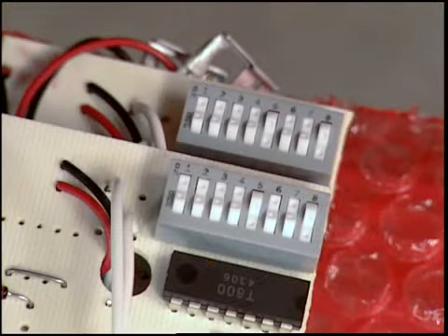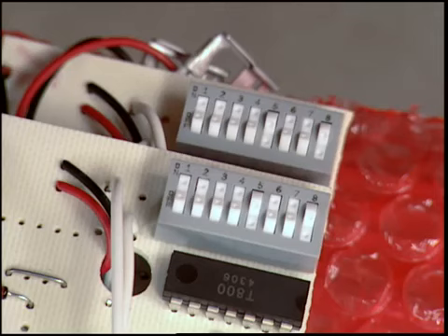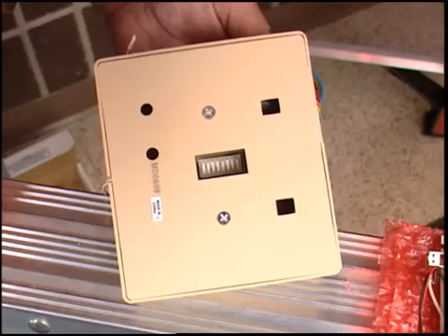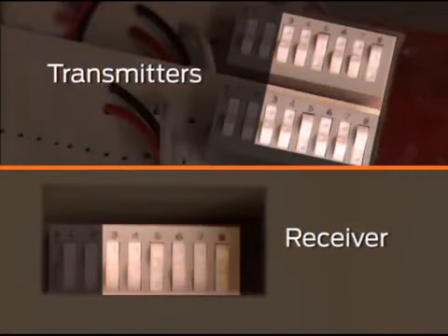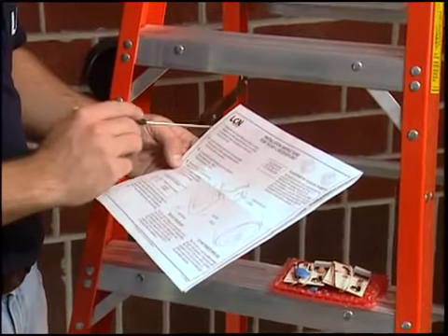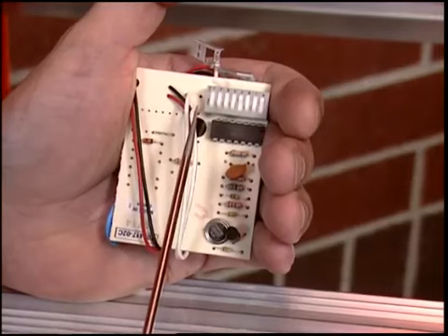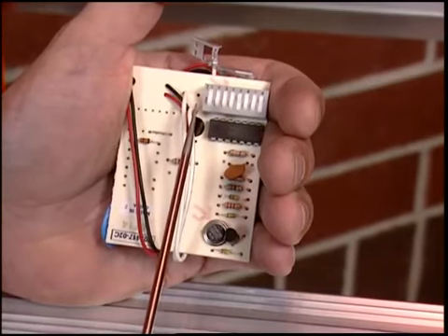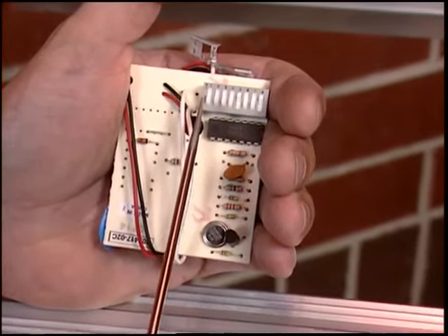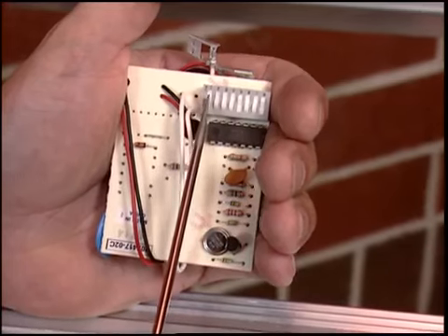Locate the circuit boards and set the 8 programming switches on both the transmitters and the receiver. In a 2-channel installation like this, switches 3 through 8 should match on both the transmitters and the receiver. See the instruction booklet for more programming details. For this installation, the exterior actuator will activate channel 1. The interior actuator will activate channel 2.